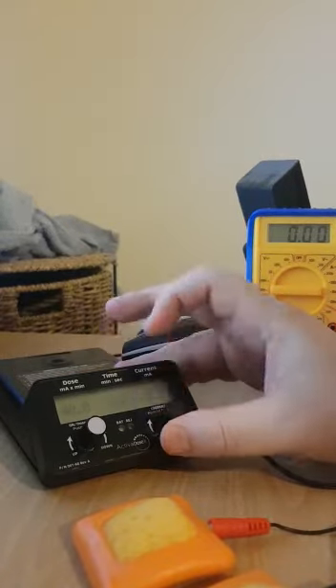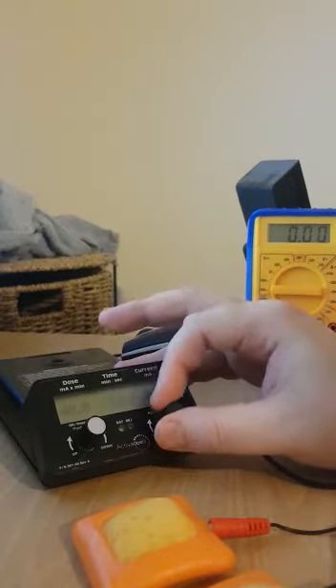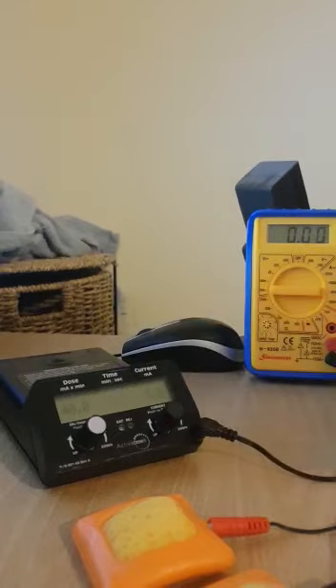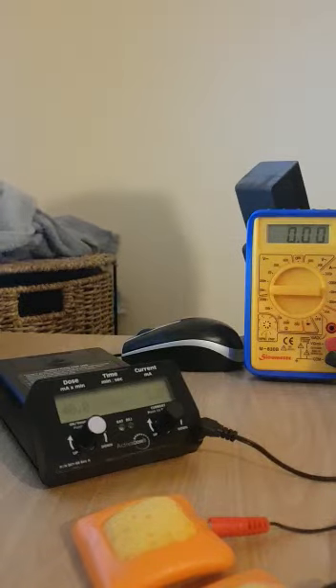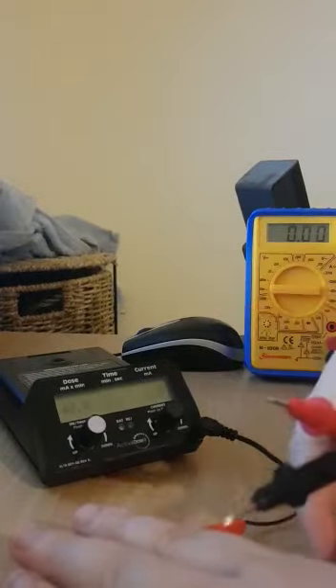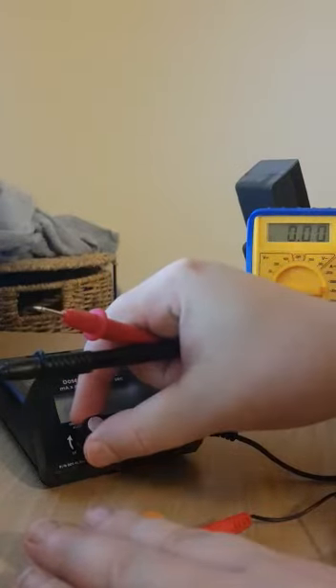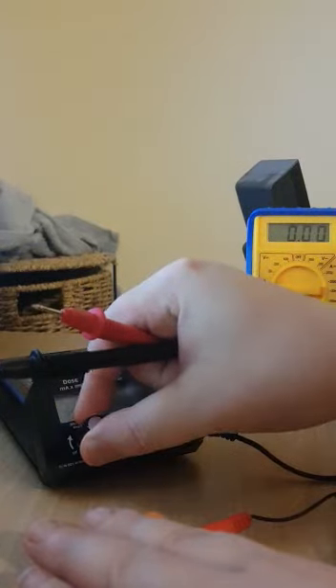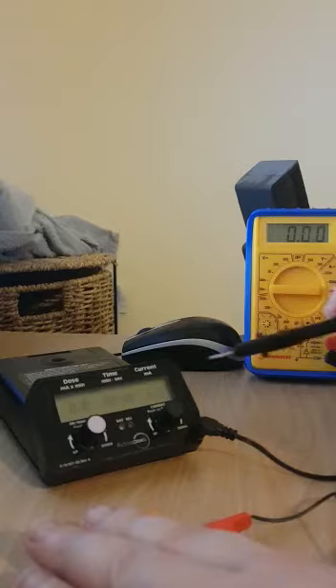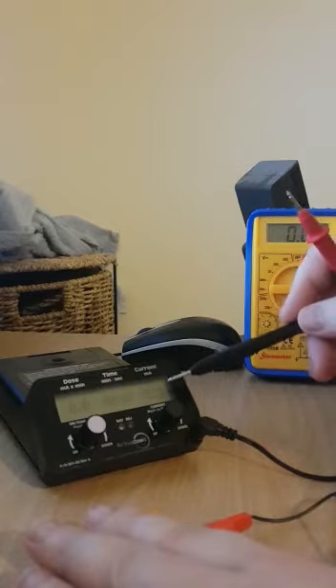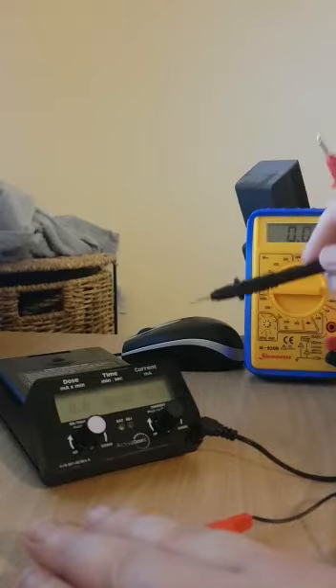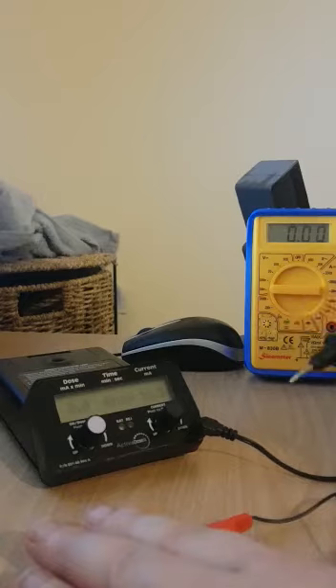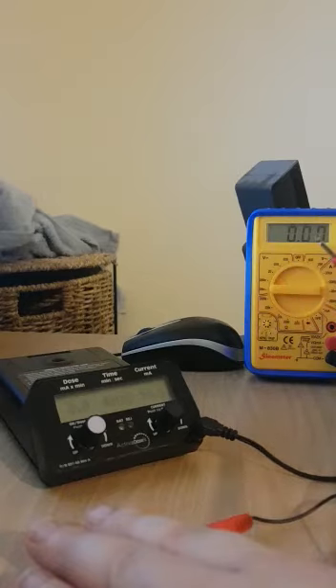Let's set this at one milliamp and start it. I've got to make contact with the electrodes otherwise it will panic and think that it's not working. So I've actually got to do that and then to start it one little click clockwise. It starts at 0.1 and starts building up slowly to the one milliamp that I've suggested.